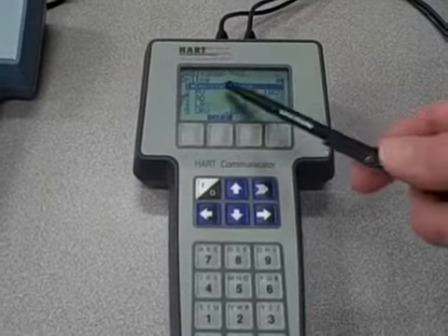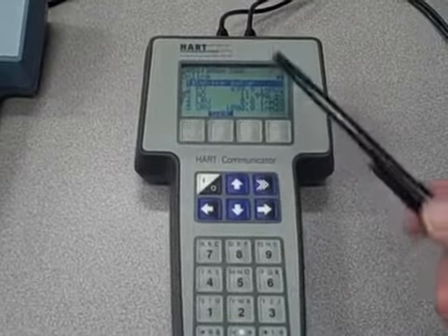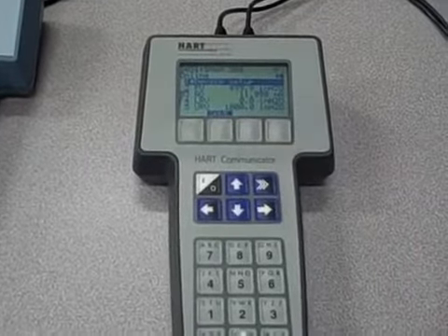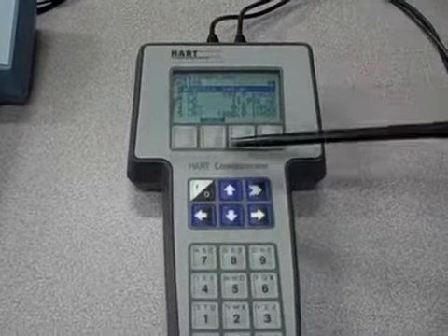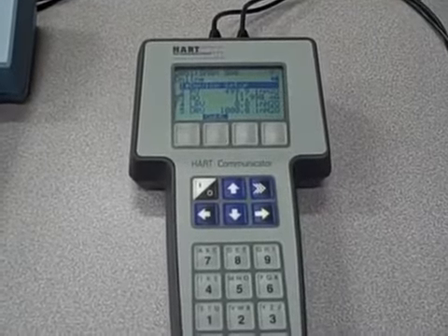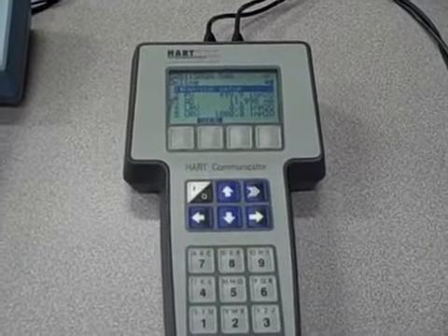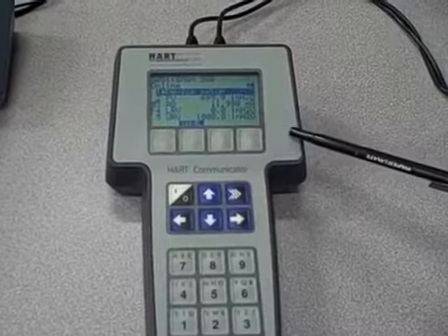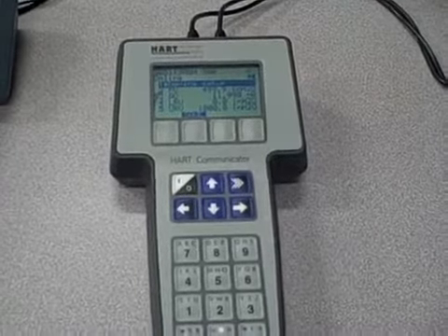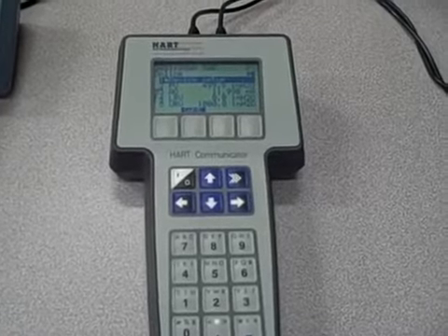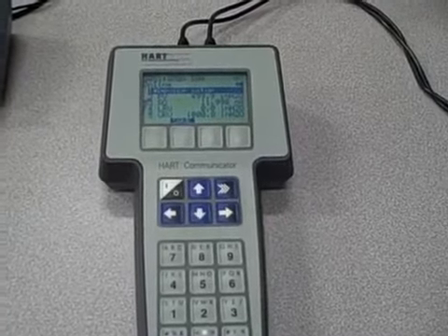It tells us the process variable being measured by the transmitter, the current output it thinks it's outputting, the range values, etc. In fact, this menu structure looks very similar to the one you see with a Model 375 HART communicator. This one's a newer communicator, and like I said, it has the appropriate DD files to be able to talk to the Model 3051 transmitter, and so it did not give us an error message whatsoever.